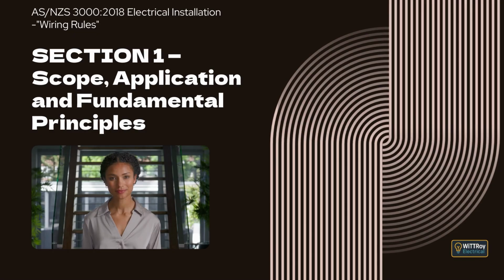Clause 1.4.35 is conductor. A conductor is a wire or other material suitable for carrying current. It does not include metallic parts that are only used to enclose electrical energy or provide structural support. Clause 1.4.36 is conductor, bare. This is a conductor without covering or insulation. Clause 1.4.37 is consumer mains. These are the conductors between the point of supply and the main switchboard. Clause 1.4.38 is contact, direct. This means touching a conductor or a conductive part that is live in normal service. Clause 1.4.39 is contact, indirect. This is touching a conductive part that is not normally live, but has become live because of a fault, such as insulation failure or some other fault condition.